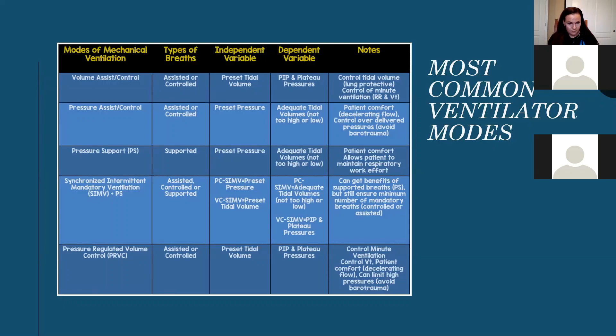All right, so let's break these down a little bit more. I'm going to come back to this slide in just a second. So we talked about SIMV. This is the one I would recommend if you have a ventilator that will allow you to set a volume, set a rate, set an I time, and also set a pressure support. This is the mode that I recommend. You're going to get a breath guarantee, but the patient is also going to be able to take breaths on their own. They're going to get a set amount of tidal volume and a set amount of breaths, but your patient will be able to synchronize a lot better.